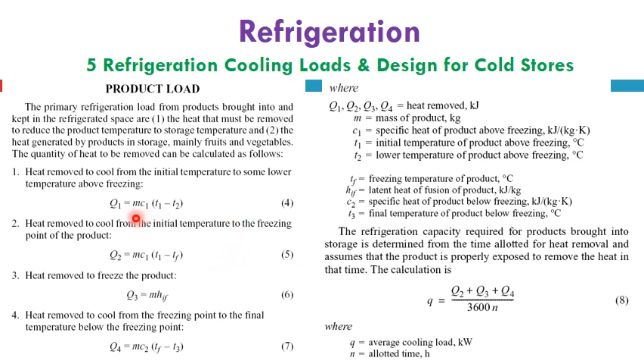So we can conclude that equation 4 and 5 indicate the sensible heat terms of heat above freezing, even as we reach the freezing temperature, as Q1 for veggies or fruits, and Q2 can be used for meats or fishes or chicken. And to continue with the freezing terms, the latent heat amount is nomenclatured with subscript number 3, the latent heat term. Then the third term to be added for freezing products is Q4, to consider the last term of sensible heat to be added.